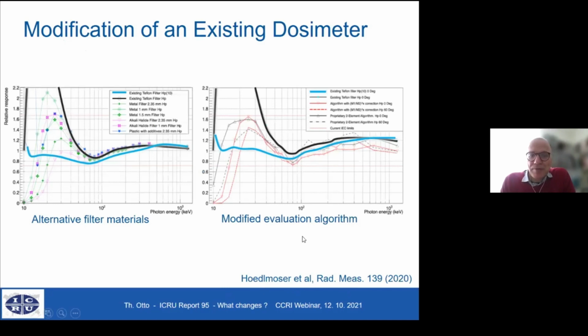Here we see work from a large dosimetry service in Europe, which is published in Radiation Measurements, where the authors have shown the response of the dosimeter in blue to the HP 10 quantity, as we have it nowadays, and to the new quantity. And obviously you see this high overestimation, and they have been generous. They cut off the plot, so you don't have to go up to 5, but I know it goes up to 5, these values here.